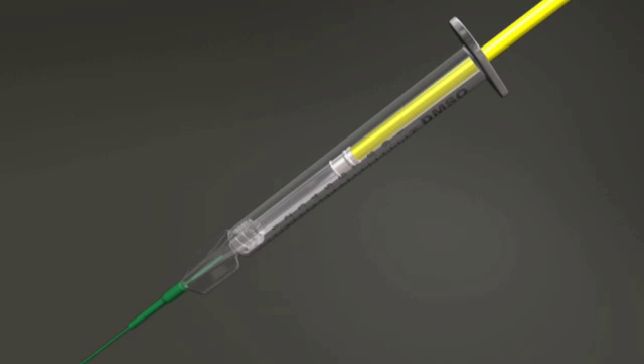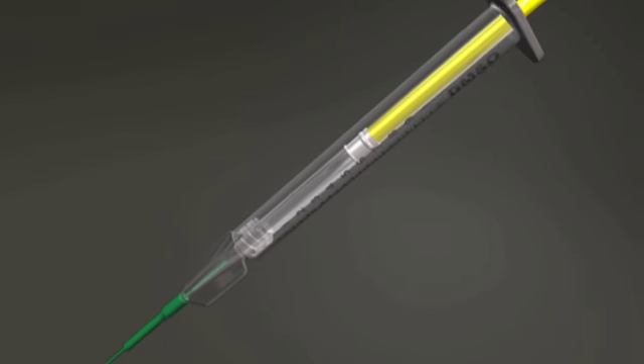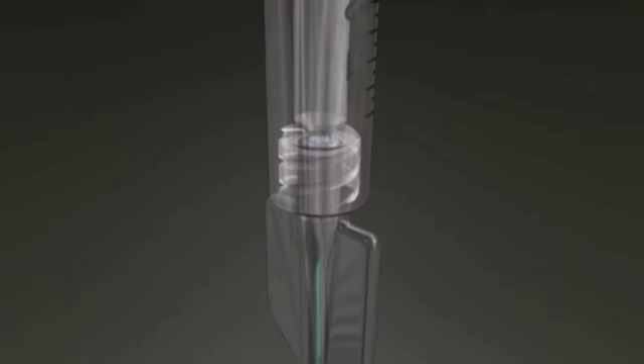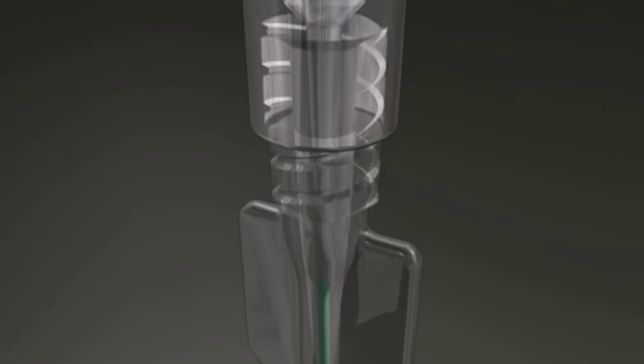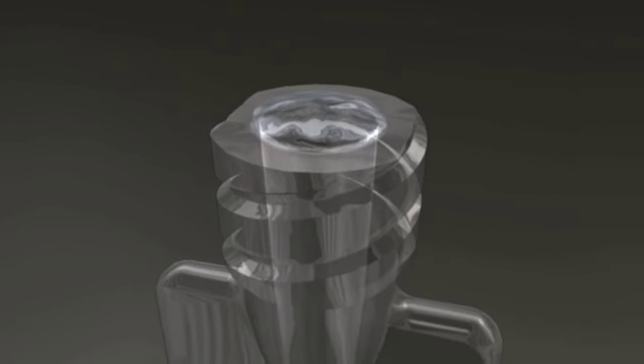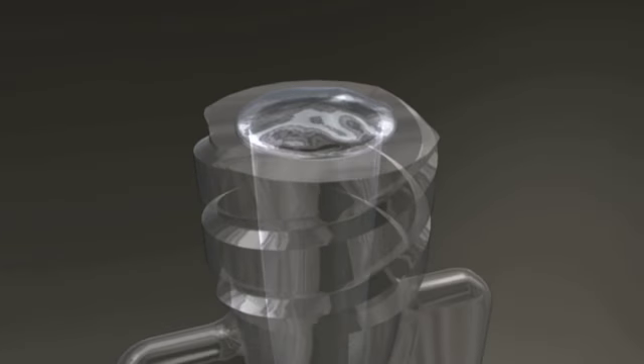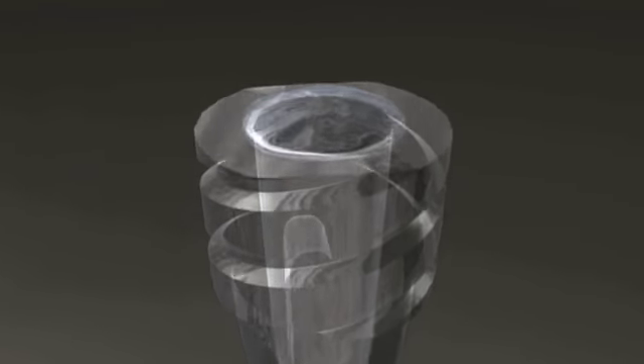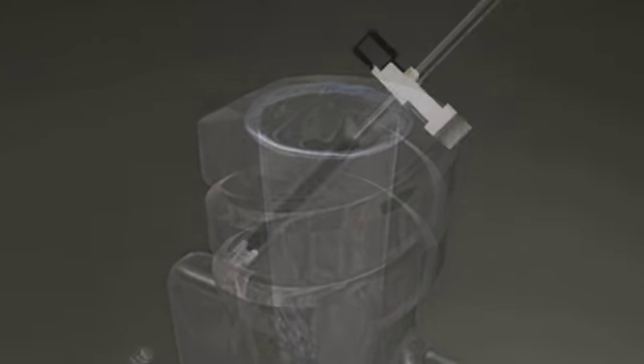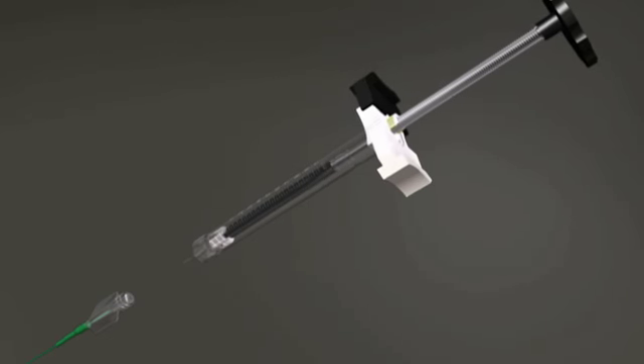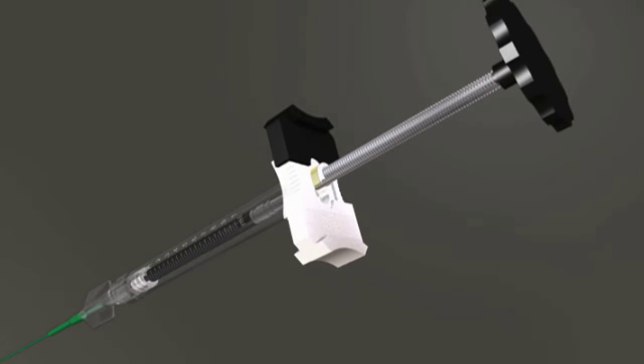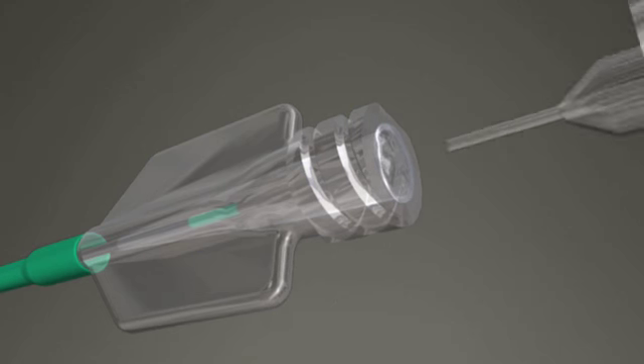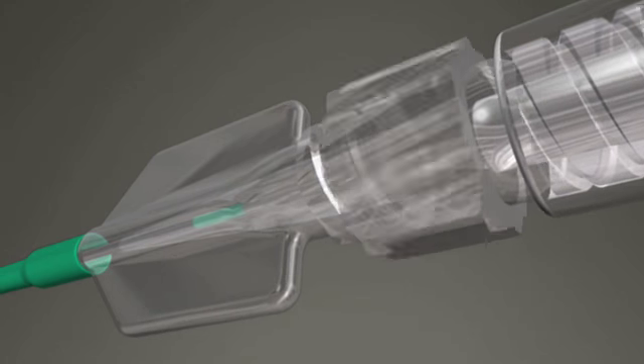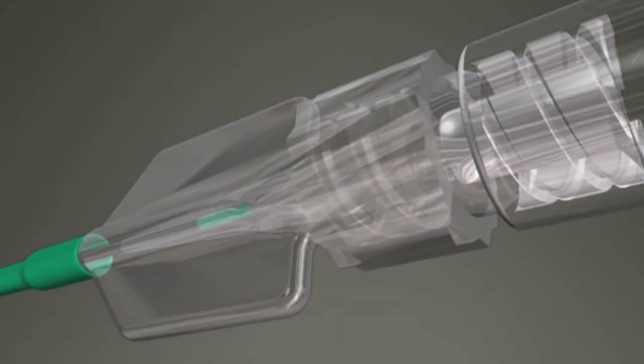As soon as the DMSO has been injected into the catheter dead space, remove the DMSO syringe. Overfill and wash the luer hub with the balance of the DMSO, creating a meniscus of DMSO in the catheter hub. Next, attach the interface device to the microcatheter hub, taking care to exclude air. With the balloon deflated, begin to inject Onyx to fill the dead space of the catheter.